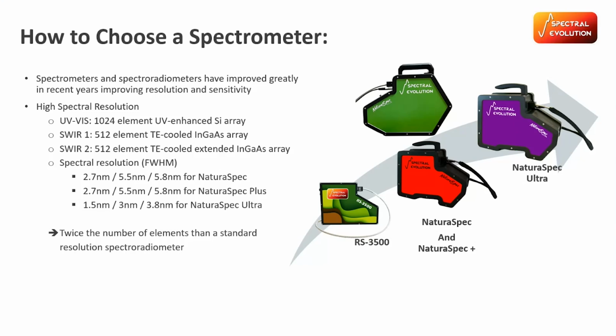For that instrument, we get 2.7 nanometer resolution in the Vis, 5.5 and 5.8 in SWIR 1 and SWIR 2. The improvement that we've made with the NaturaSpec Plus is an internal battery, as well as a smaller form factor. So it's lighter, easier to transport in the field, and it has an integrated battery inside the instrument that you can hot swap, so you never have to disconnect from the instrument. That is our most modern instrument, and it's the new standard for remote sensing and field measurements.